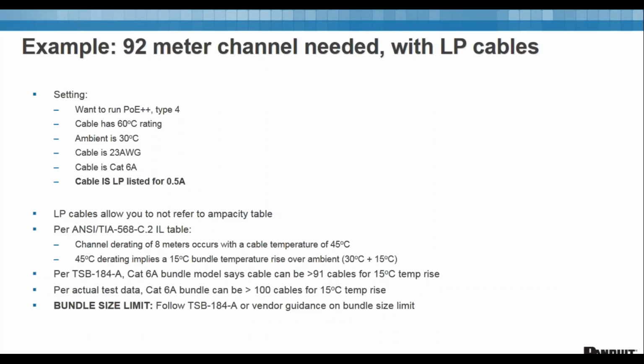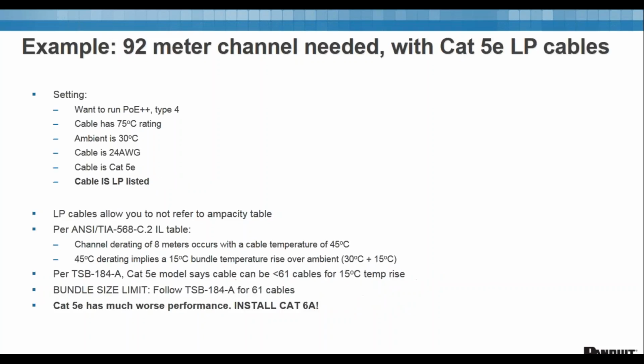Now, if all you've changed here is that you're using an LP cable, what we see is that this shifts, right? LP means you don't have to worry about your bundle size per the National Electric Code, but now you should be more concerned about the impact on performance. And for performance, depending on what you're looking at, you can either be greater than 91 cables per TSB, or per actual test data, you can go even bigger than that with 6A. So now your bundle size limit shifts from the NEC to being concerned with performance. So you can actually go a little bit bigger when using LP cables.